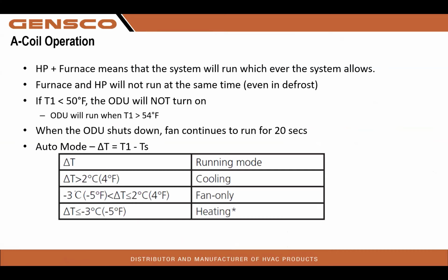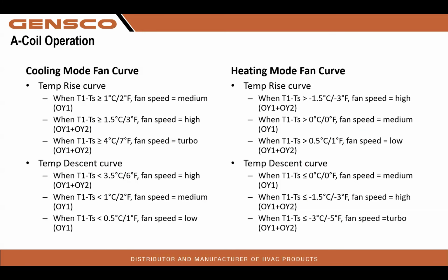When the outdoor unit shuts down, the fan continues to run for about 20 seconds. And by the way, when that unit shuts down in a call for cooling or heating, it does have a coil clean feature, which will make the condenser fan motor run backwards after the call is terminated, and it will run for about 30 to 45 seconds and blow any cottonwood or anything off the coil, which is a great feature. These are pressure and temperature and fan curves.